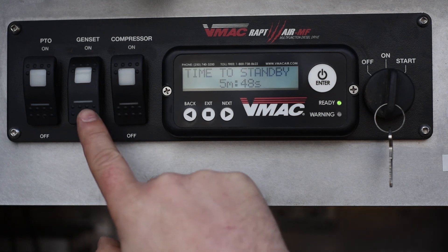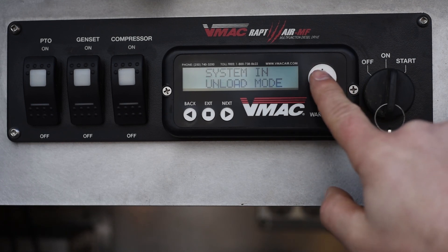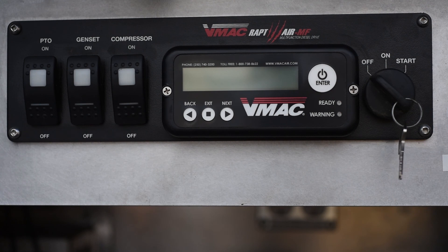To turn off the system, turn off the air compressor, genset, and/or PTO switch, then press the display box on/enter button. The system will go into unload mode for about 25 seconds. Turn the key to the off position to fully power off all electronics. The key switch can also be used to shut down the system; however, this will directly turn off power to the control system and the system will have to go through its system check before being able to restart.